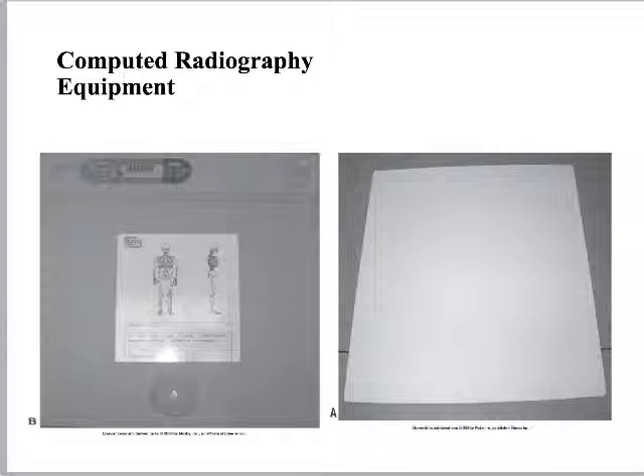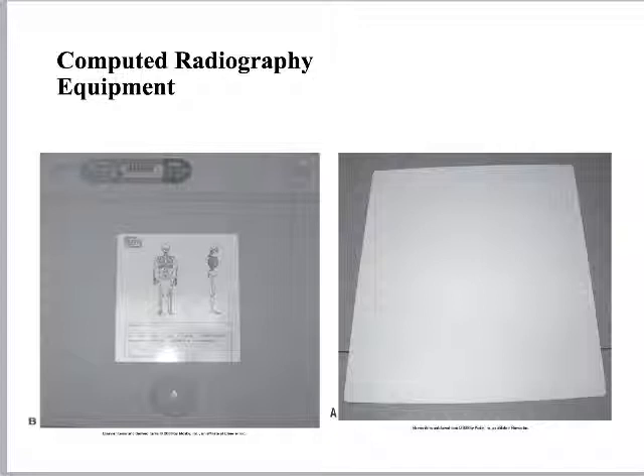Computed radiography actually works a lot like film, which was significant — a lot of technologists, myself included, made the mistake of thinking about CR exactly like film. They're really very different even though the workflow is similar. The first similarity between CR and film is that they both have a cassette. Inside a film-screen cassette you have intensifying screens and a piece of film kept in the dark. With CR, it has a photostimulable phosphor plate made out of barium halide or fluorohalide.